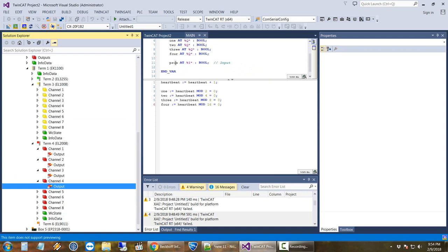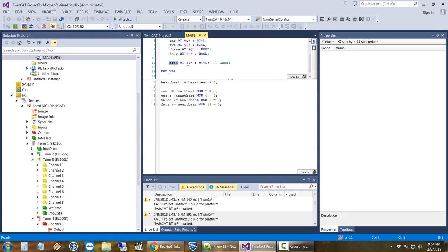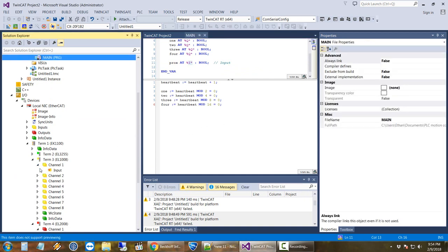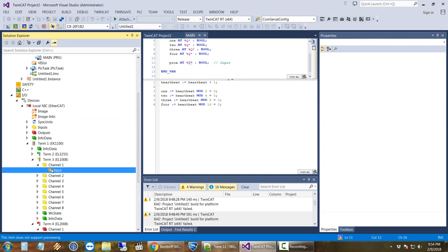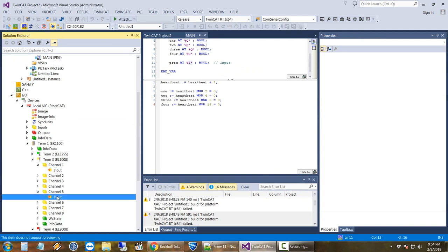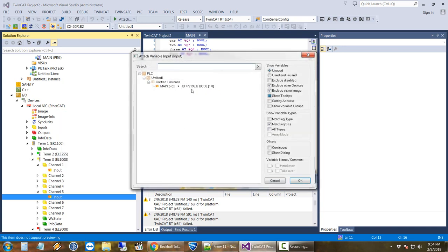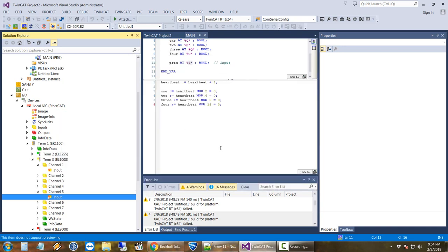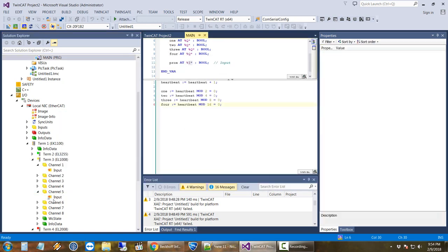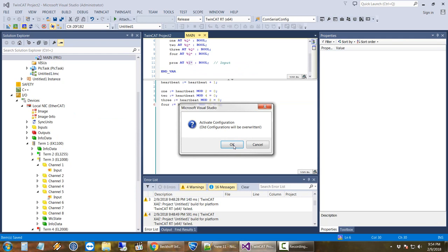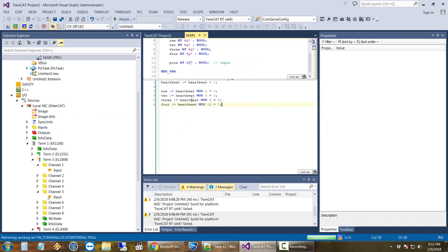So our other one, our prox, this is a percent I star saying it's an input. So it's coming into our program and we can make decisions based on that value and affect the outputs. So we'll just feed this into, let's see where I wired it, 1, 2, 3, 4, 5 I believe. So we'll wire that into 5. And there we go. So now once you save it, none of this happens and takes effect until you activate again. Just with I.O. changes. Most of the code changes you can do online without shutting down the system. OK. So I'm activated. I'll log back in. And I'll hit run.